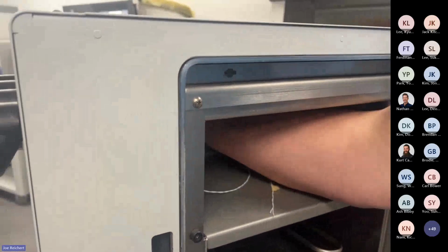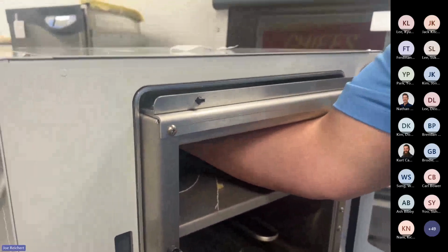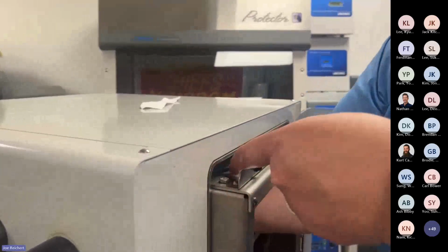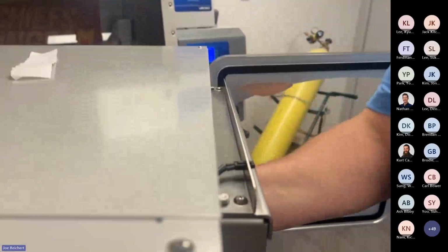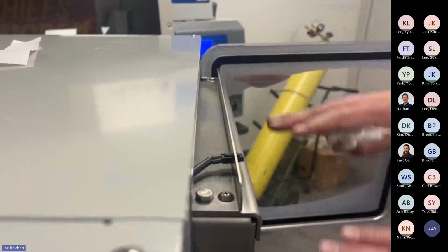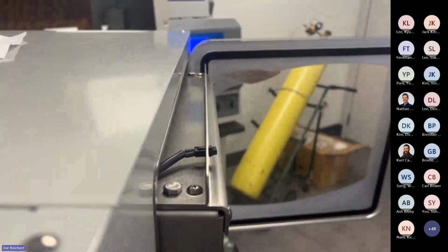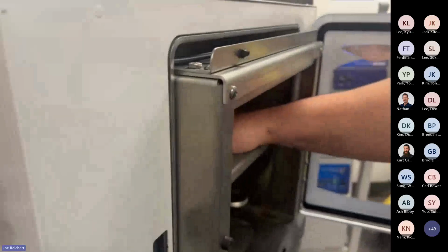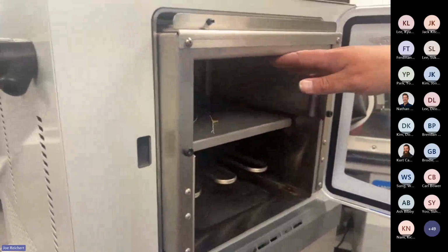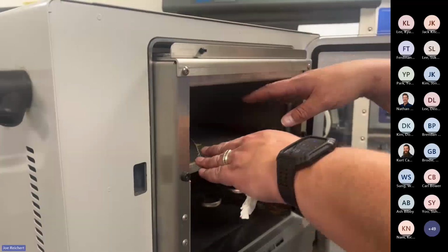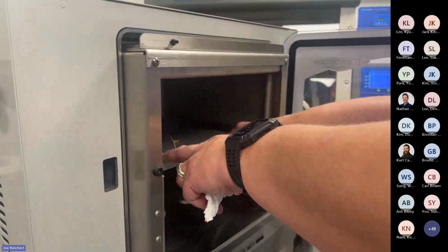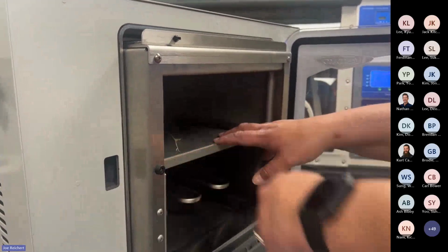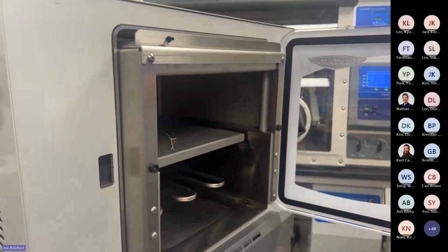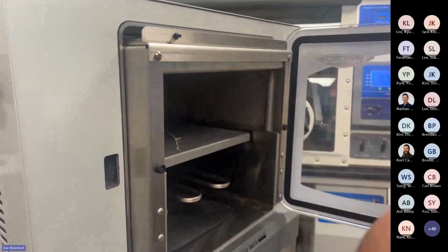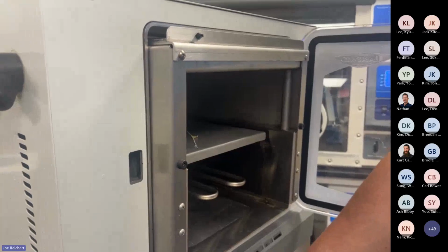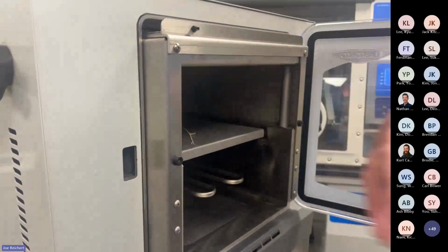Now in the back, you can't really pull this too far out because there is some wiring. You have the wires for your sample probe. This unit also has a level sensor so that if somebody puts vials only on one side of the shelf, and then as that shelf comes down, if it starts to tilt, it's going to knock those vials over. It's going to break vials. So you don't want it to do that. So the machine will stop the operation when it gets more than a 5% turn. And it'll open a valve that's behind this panel to release the air out of the bladder so it doesn't continuously try to pump it up.